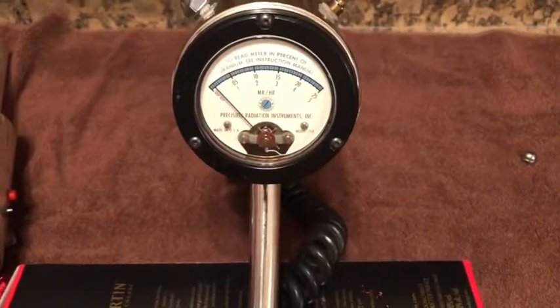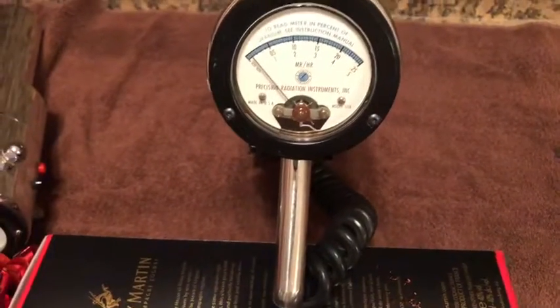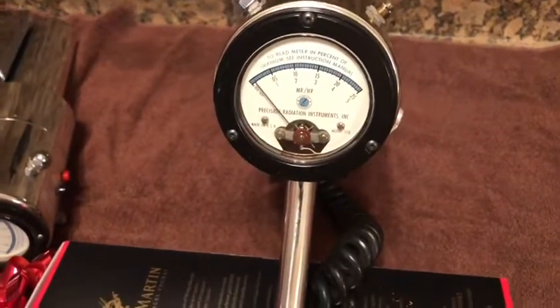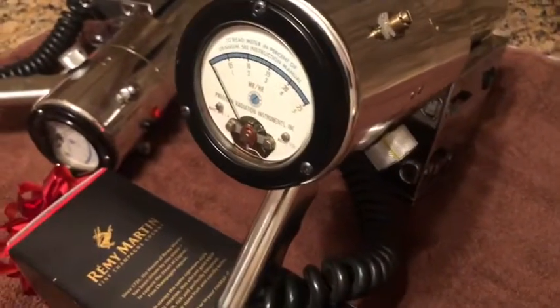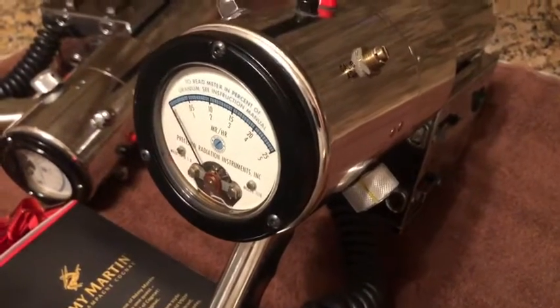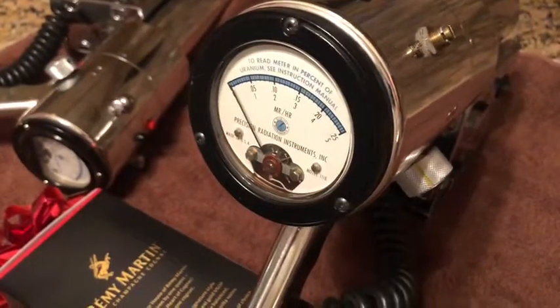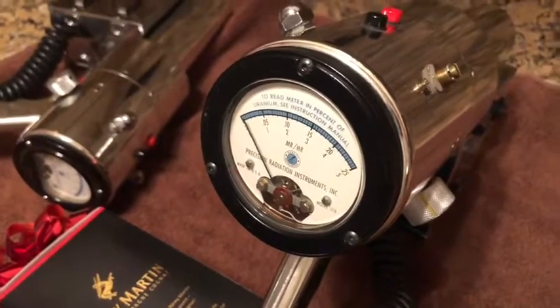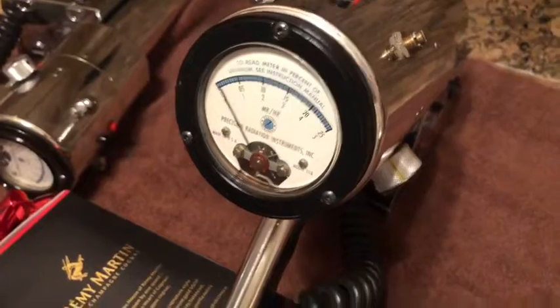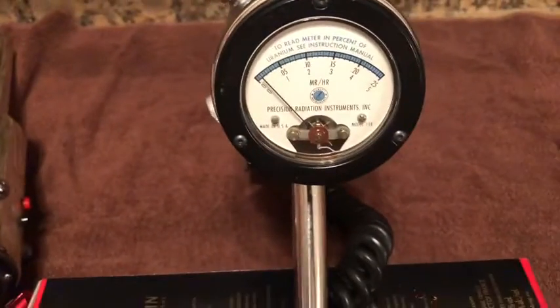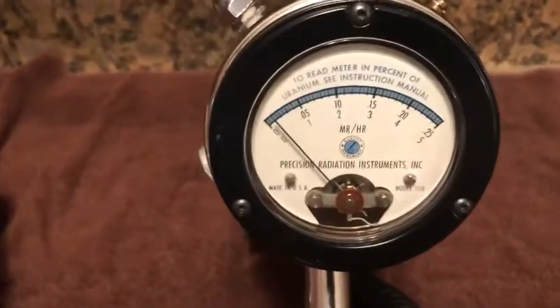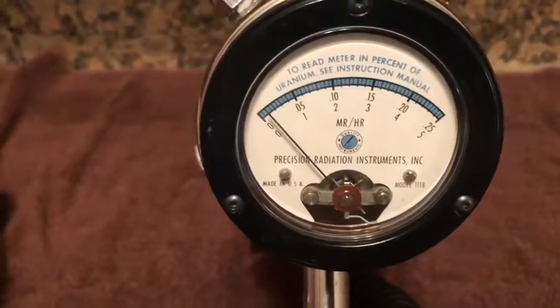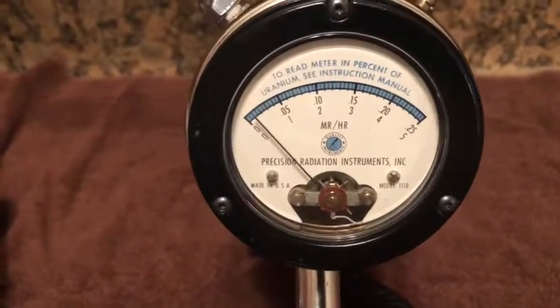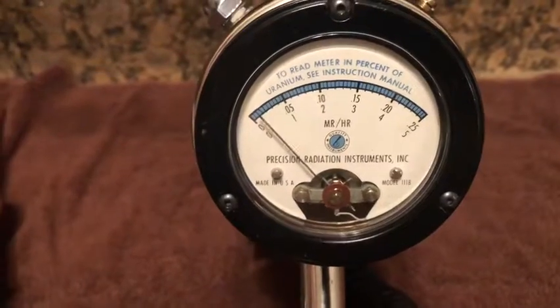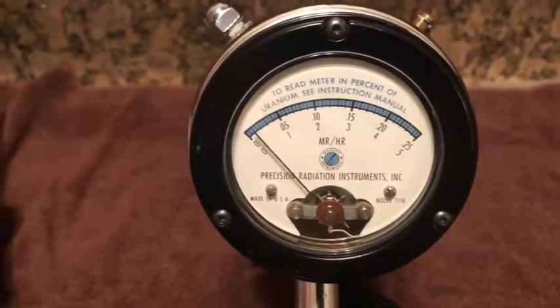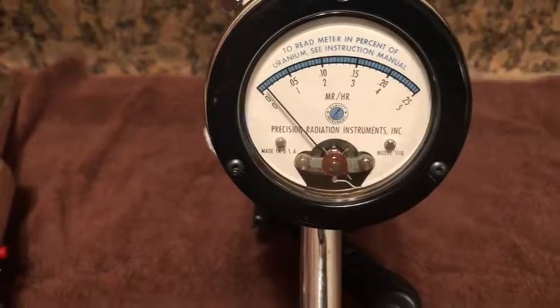You could use a pulser, but there is no input on these things to calibrate with a pulser. You would have to take this apart and put some jump leads into the amplifier circuit in order for it to read pulses from a pulser. And these things don't read in counts per minute or counts per second, so even using a pulser might be difficult. You probably have to use some sort of calibrated test source.